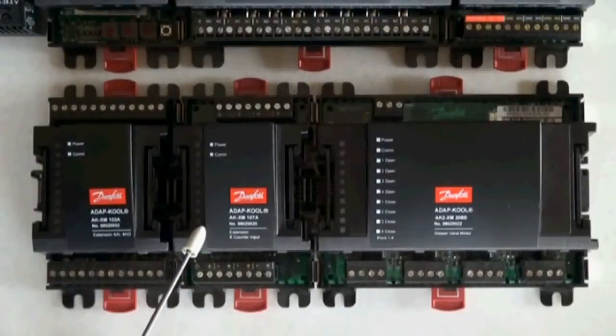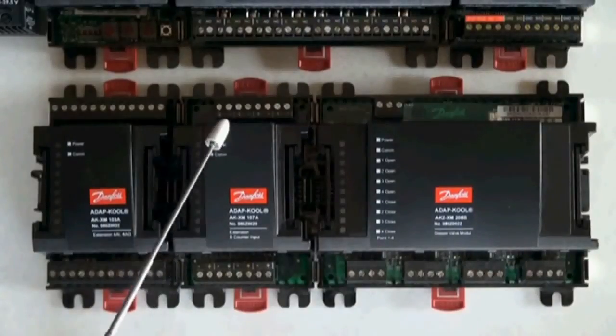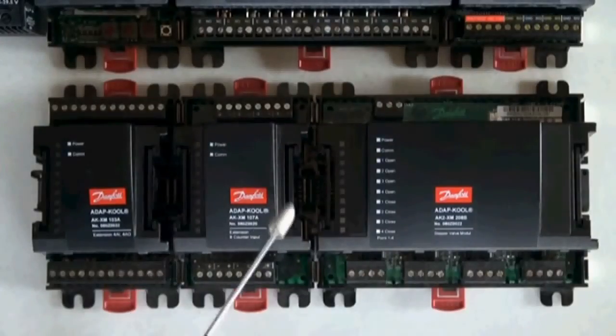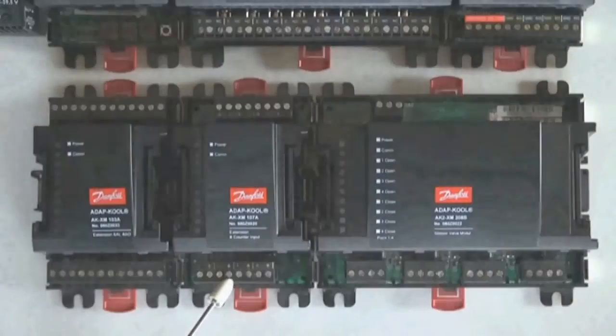Next you see the pulse module, used for reading pulses from kWh meters and other pulse output devices. We have 4 inputs at the top and 4 inputs at the bottom.